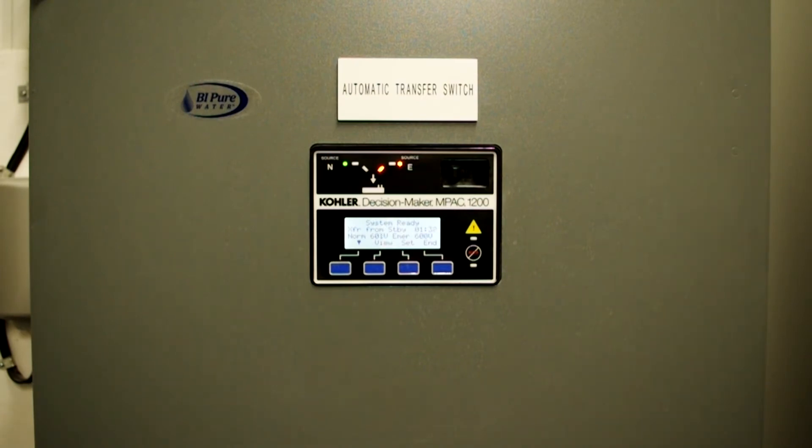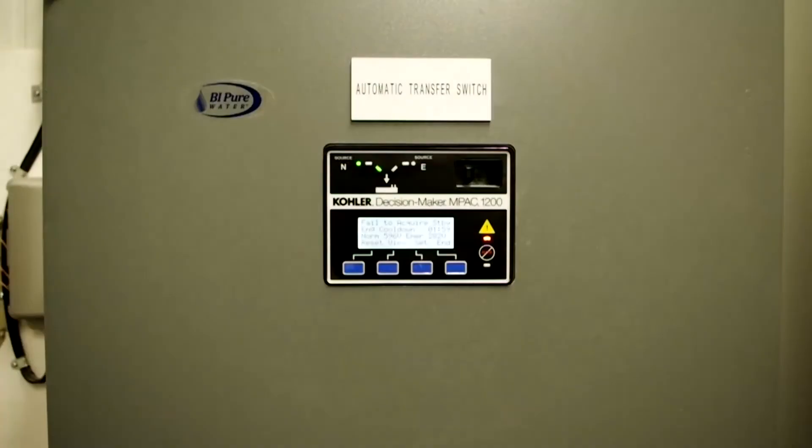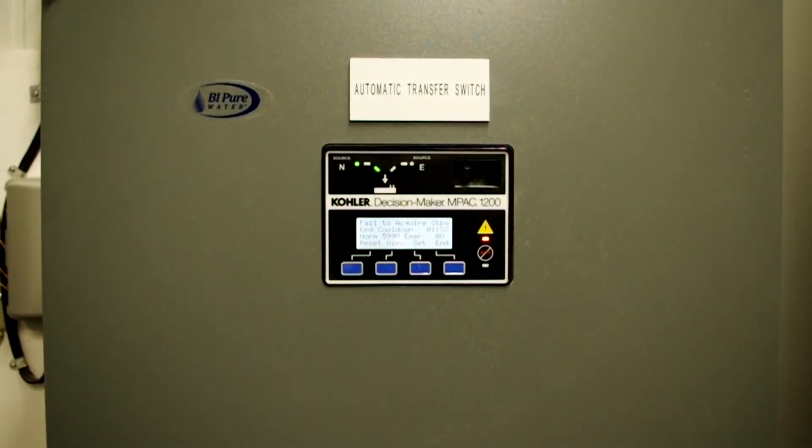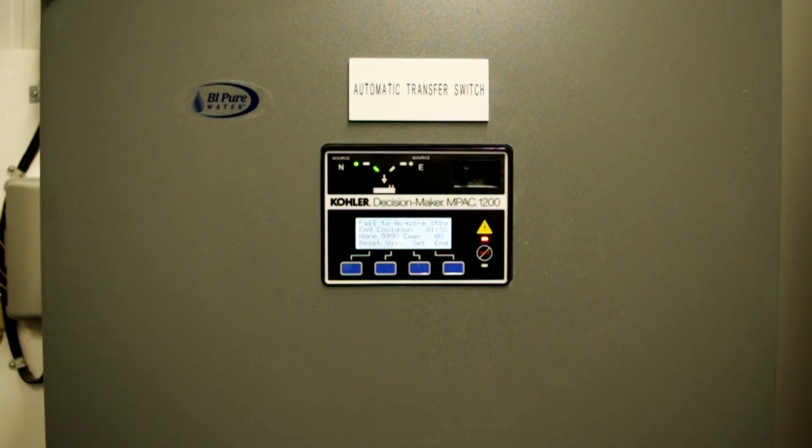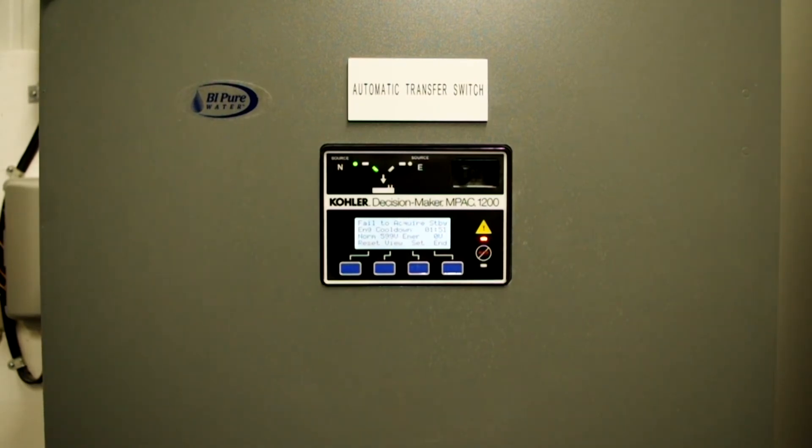And now we just let that go for two minutes. We're going to turn it back to normal power. If the power went out again, there's an engine cool down of two minutes. You can see on the screen. So if the power went out again, it still will not start up for another two minutes.